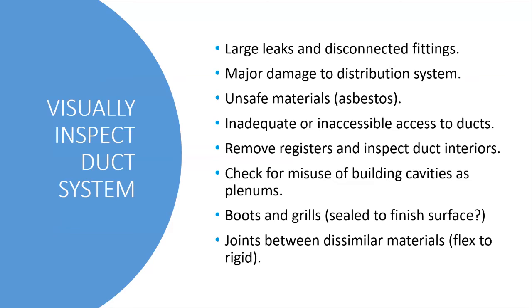When you're visually inspecting a duct system, you're looking for large leaks, disconnected fittings, or other kinds of major damage to the ducts. You're looking for things that will make it difficult or even dangerous to repair, like asbestos or inaccessible ducts. With registers removed, you can inspect the condition of the inside of the ductwork, or if wall or floor cavities are being misused as plenum, or if the boot and grills have been sealed to the finished surfaces. You should also be assessing the condition of the joints in the ductwork, especially the transitions from one type of material to another, like from rigid to flex ducts.